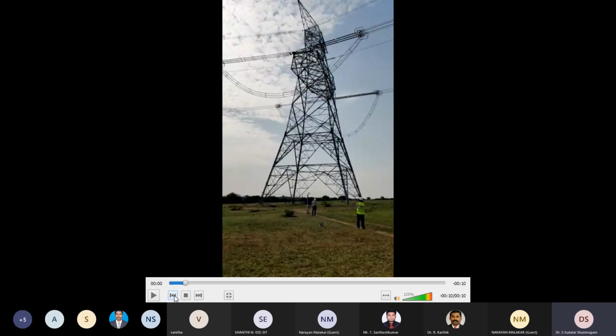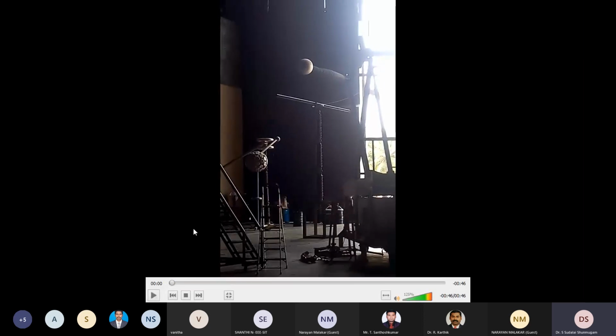That particular test you have seen was taken from CPRI Bangalore. Anyway, I'll play only the flashover part again. You can see the arc started from here and ended here. Why? Because the line is coming from this end and the ground part is here. That is the reason the arc started from the line end and gradually propagated to the ground end via the air. I'll play again. Please look at the arc propagation. It will start from the line end and move towards the ground end.